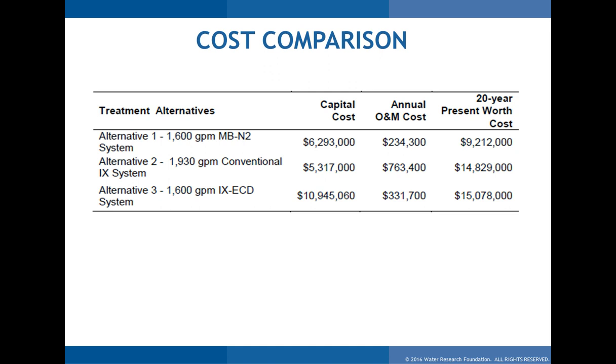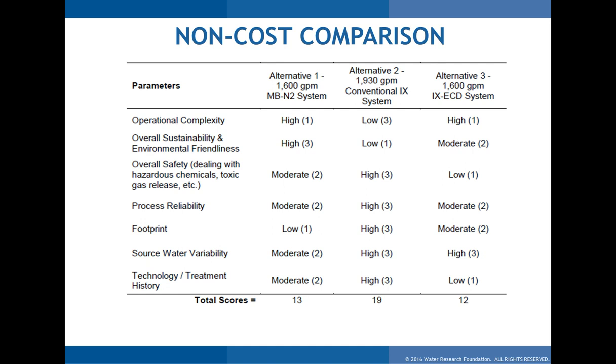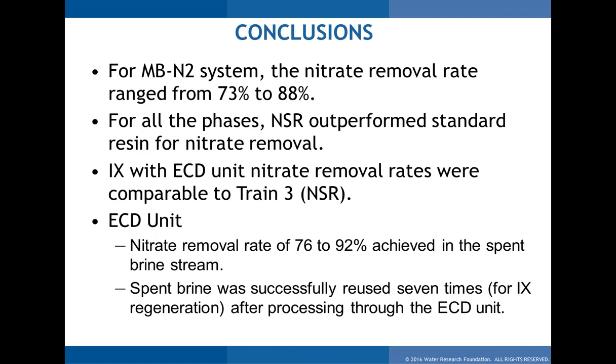The cost summary shows capital ranging from $5,000 to $10,000 per GPM, annual O&M from $200,000 to $760,000, and a 20-year present worth of $9 million to $15 million. The microbial system shows significantly lower present worth costs, driven strictly by brine disposal savings. A non-cost comparison using a ranking scale for operational complexity, sustainability, safety, reliability, footprint, and technology maturity showed conventional ion exchange scoring highest, as expected — it's proven technology used here for 10 years — versus scores of 13 and 12 for the other options, providing another input to the decision-making process.